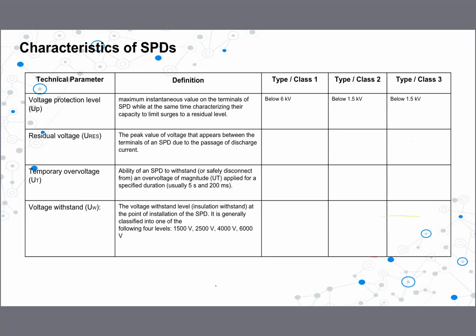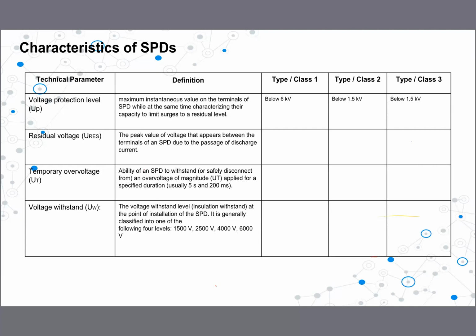Then residual voltage, right? Residual voltage is a peak value that appears between the terminals of the SPD due to the passage of the discharge. When the discharge current goes through, at that time the voltage is the residual voltage. Then temporary overvoltage value. When these surge protectors are connected into the system, there can be a temporary overvoltage. So the surge protection device, when it is not in operation, when it is in standalone condition, should be able to withstand these temporary overvoltage values, right? This is also given on the surge protection device.